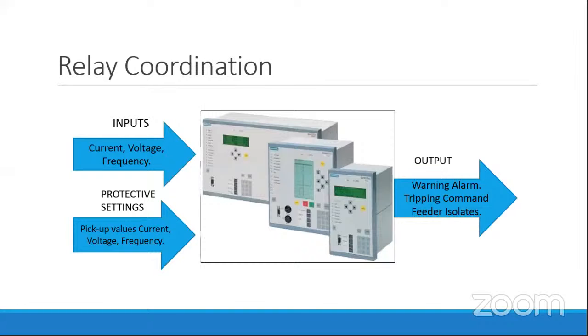These relays have many features, like current, voltage, and frequency measurement, as I said earlier. It also measures the power which is being supplied to that particular network. And likewise, it has many features for connectivity with automation. It can also be augmented with upcoming technologies, like PLC and SCADA. So for better advancement, the electromechanical relays are nowadays getting replaced with these numerical relays, which are very fast in operation, and many protection functions are covered in this single unit.